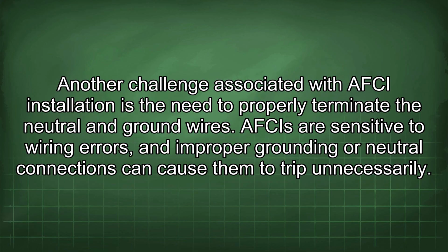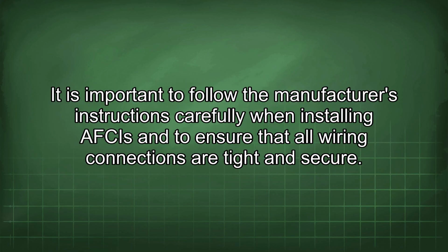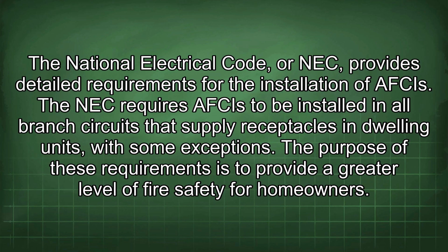Another challenge associated with AFCI installation is the need to properly terminate the neutral and ground wires. AFCIs are sensitive to wiring errors, and improper grounding or neutral connections can cause them to trip unnecessarily. It is important to follow the manufacturer's instructions carefully when installing AFCIs and to ensure that all wiring connections are tight and secure. The National Electrical Code, or NEC, provides detailed requirements for the installation of AFCIs.